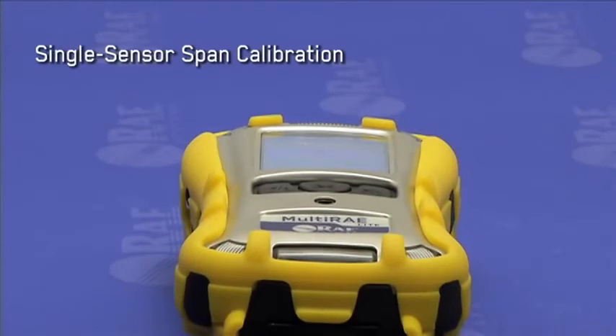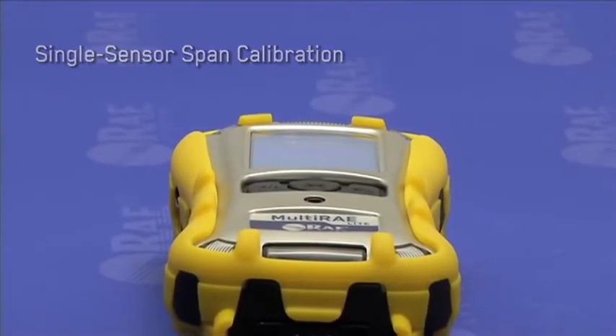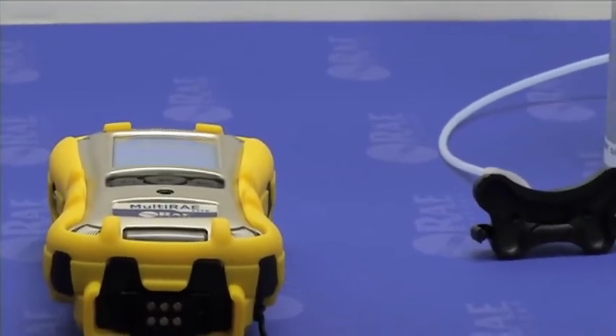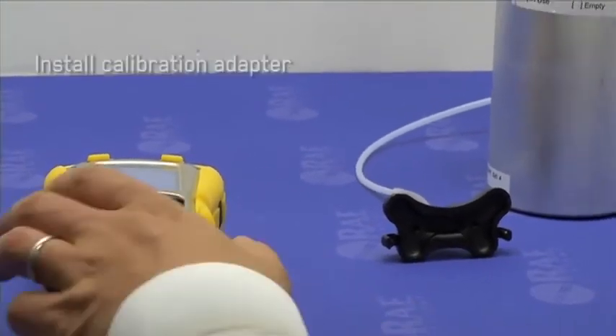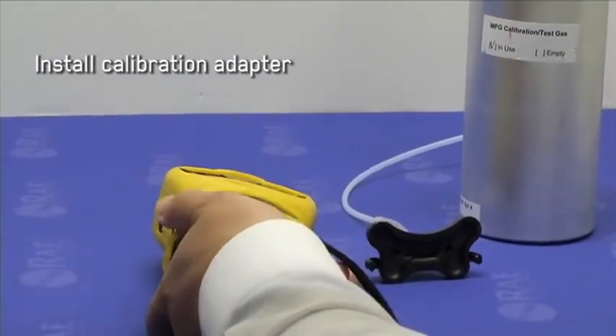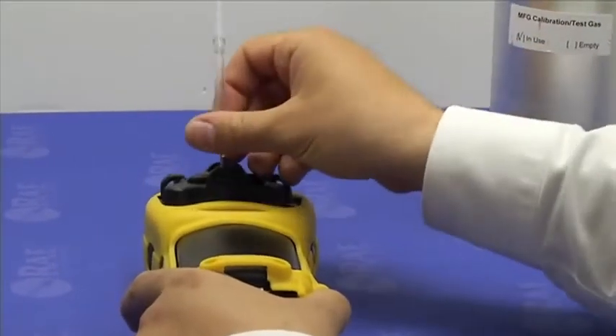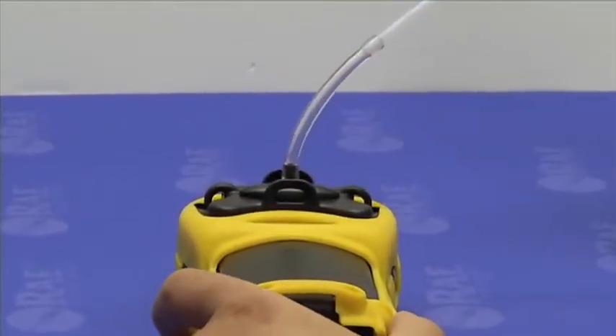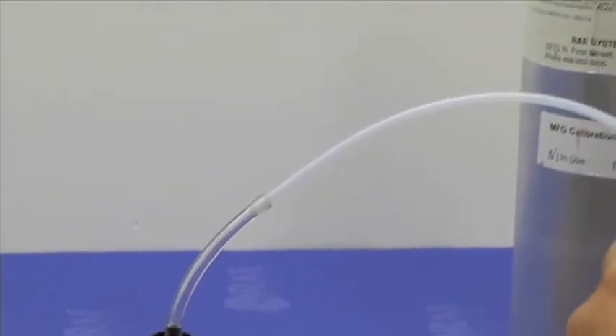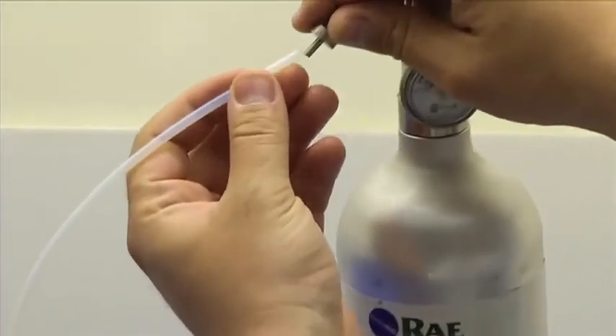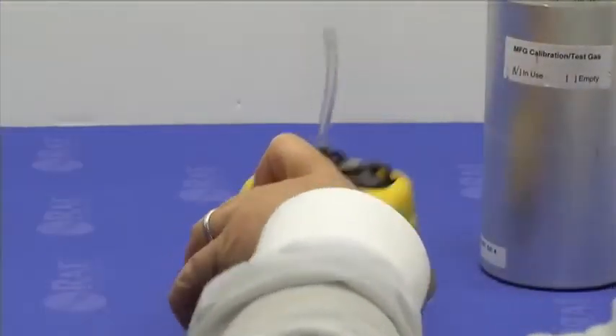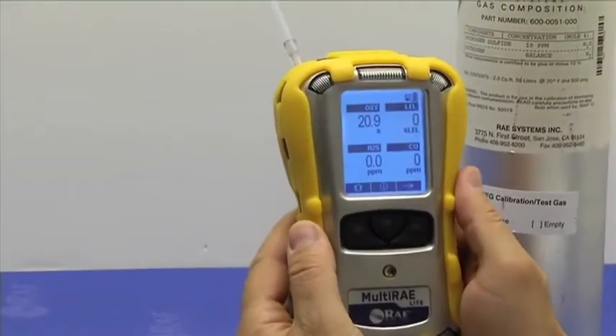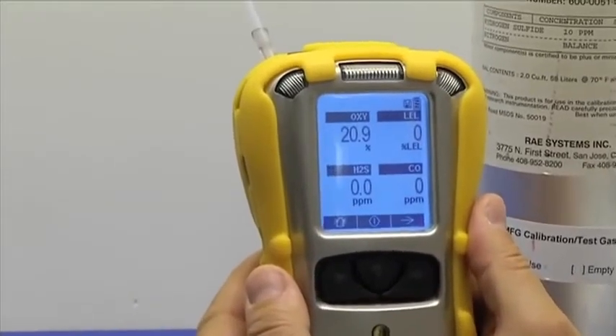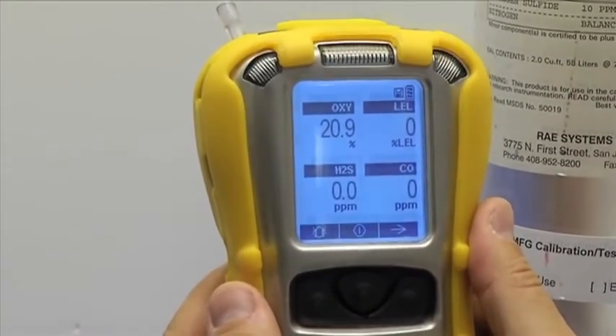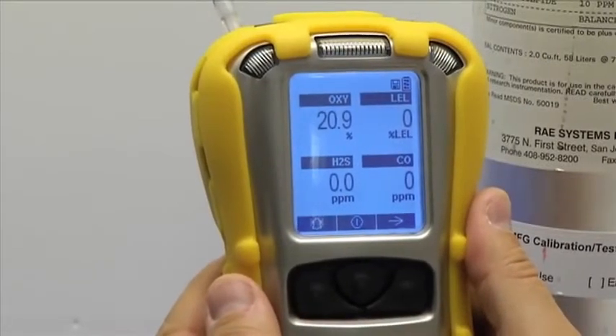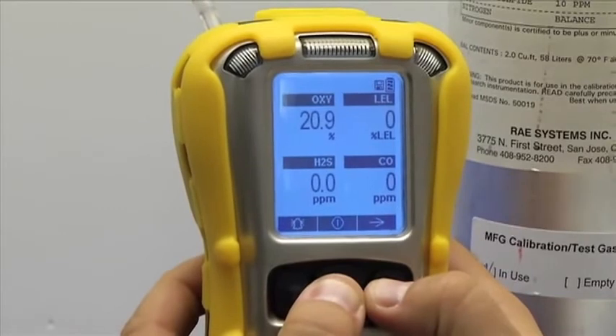Let's review the single sensor span calibration process using the MultiRAE Lite diffusion as an example. Let's say I wanted to calibrate the H2S sensor. I first need to install the calibration adapter, and then connect it to the calibration gas cylinder. Next, I would turn the instrument around so that I can view the screen readings. To calibrate the H2S sensor, I need to enter the programming menu first. I can do so by pressing the Mode button and the End button simultaneously until the password screen appears.